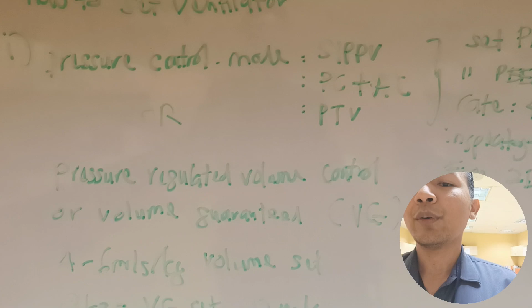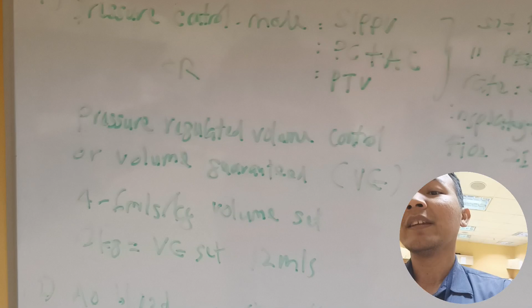So probably within plus 5 from the generated pressure. Okay, so why is it called pressure regulated volume control or volume guaranteed? Because the machine will try to achieve the tidal volume that you set, but this will regulate the pressure as well.